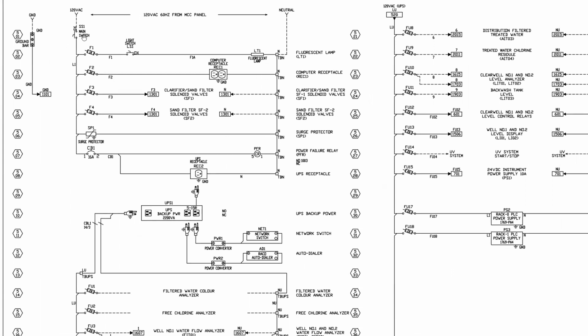They had a main switch here. So a selector switch to turn power onto the panel. Then we come into fuses. So we've got 120 volt coming in, line 1. So all of these terminal points are going to be line 1. So line 1 will come into this side of the fuses. Notice how they're all lined up nicely. This is preferable. So all of your devices that are going to be jumpered together, line them up. It's very pleasing to the eye.